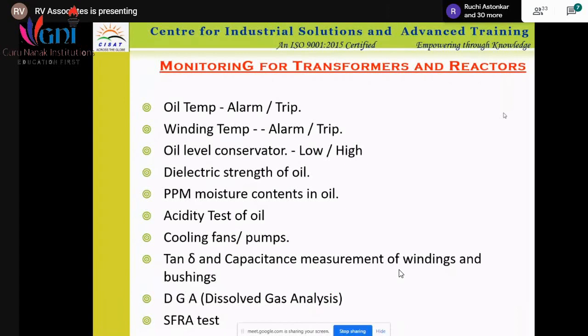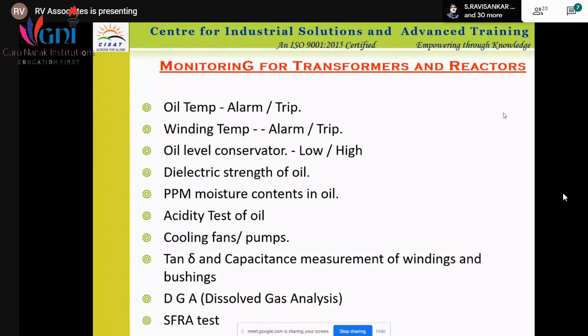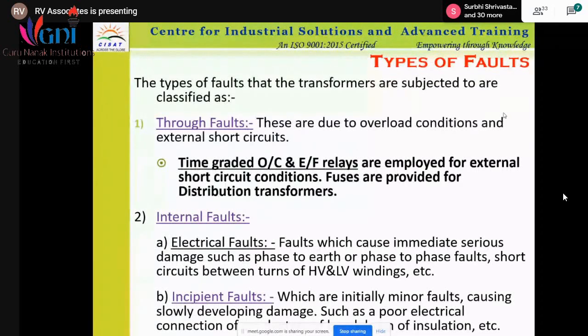There is an FRA test. Normally the FRA test is done while commissioning the transformer. If anyone gets a chance, you can do this test, but it can be done only during commissioning, or if the transformer failed and after maintenance has been done, when you restart the transformer. Then various relays are used for the protection system, like for through faults. Time-graded overcurrent or earth fault relays are used, which sense these faults and trip the system.